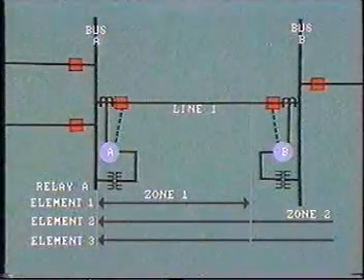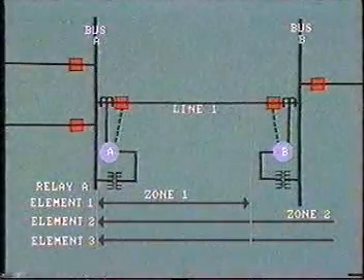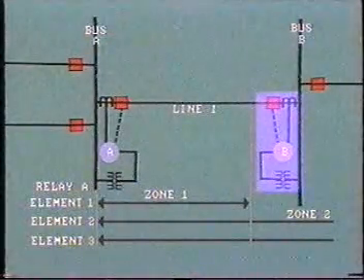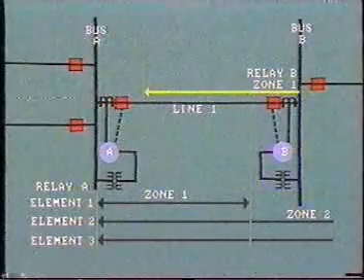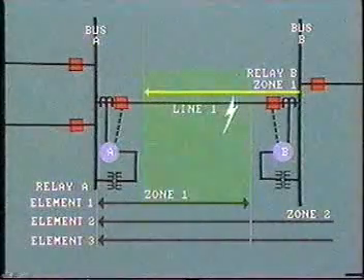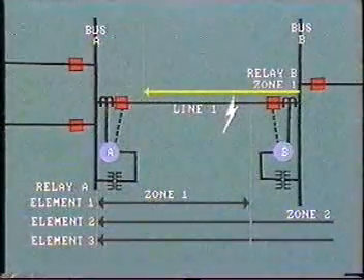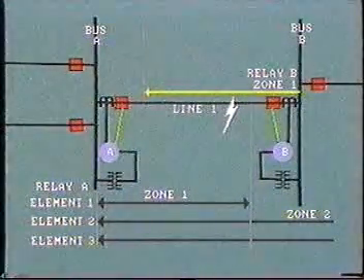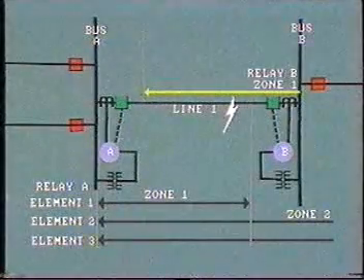Also, for protection of line one, a set of distance relays will be installed at bus B looking towards A. The first zone elements overlap, and a fault occurring within this zone would cause the instantaneous operation of both relays and the opening of both breakers.